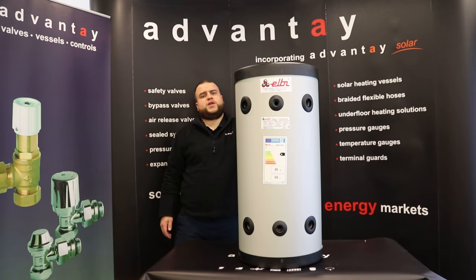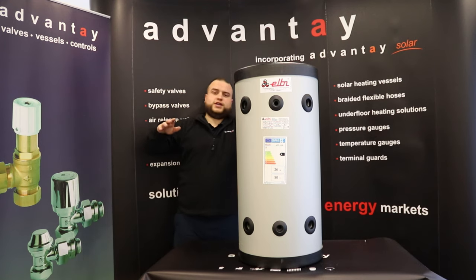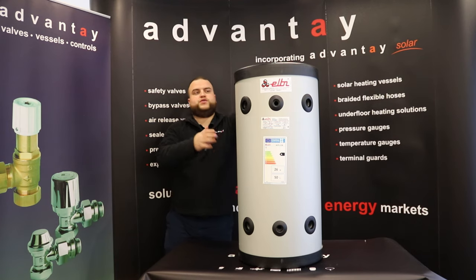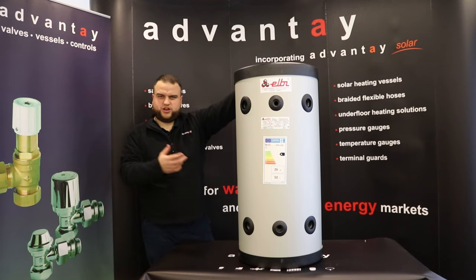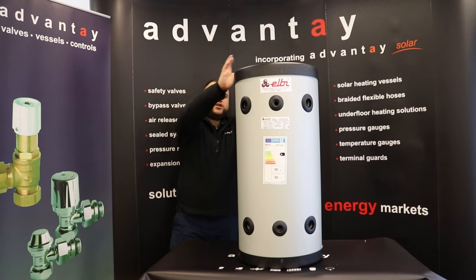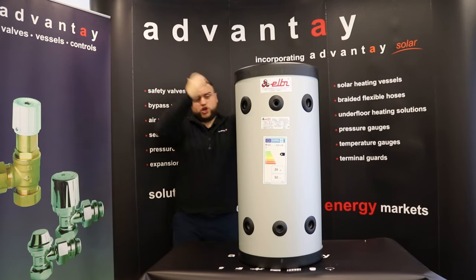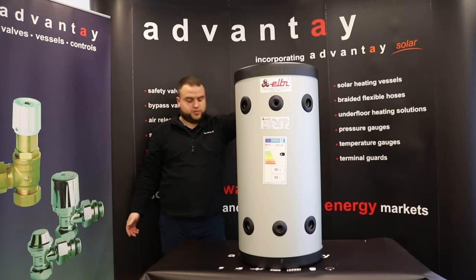Technically, the minimum working temperature is minus 10 degrees and the max working temperature is 95 degrees. I'm sure people won't have any problems staying within those limits, and it also means that if you did want to put it in a room without great insulation that could get quite cold, you'd still probably be all right. It's made of carbon steel with insulation around the outside, and it comes with a two-year warranty — pretty standard for Elbi; most of their vessels and tanks come with a two-year warranty.